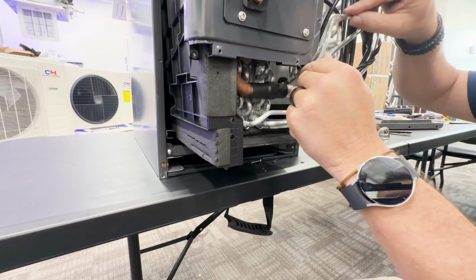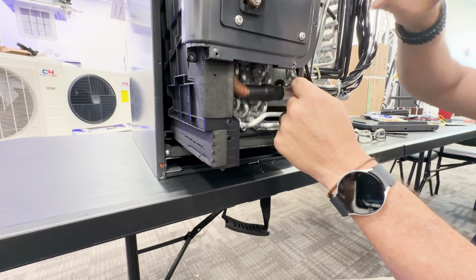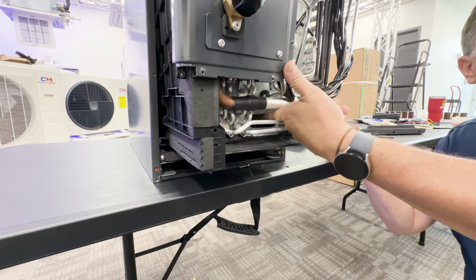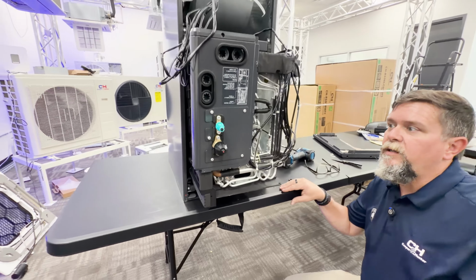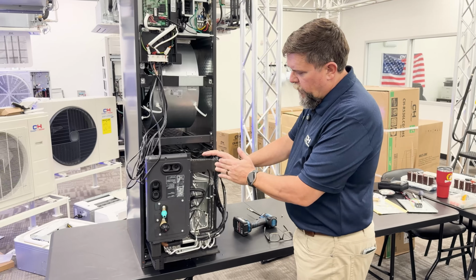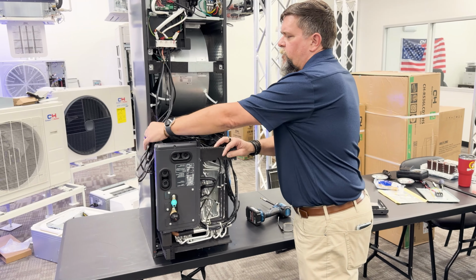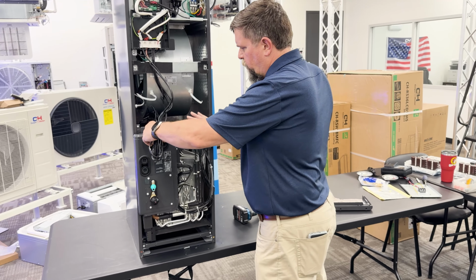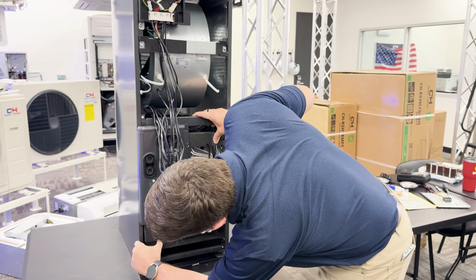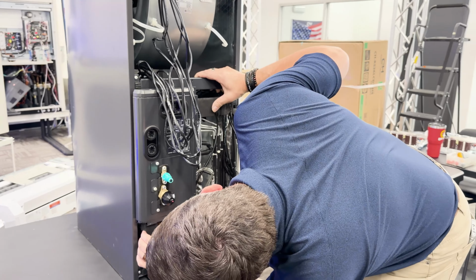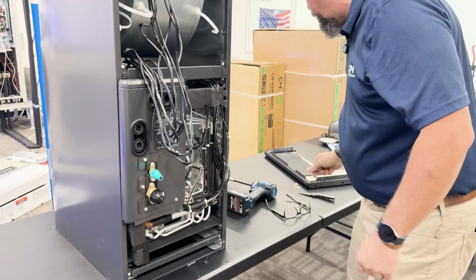Gently tuck the wires back up here, so that way it's in the airstream when it's on the downflow side, getting an accurate room air reading. With the wires protected and the thermistor relocated, now we can gently push the coil back in. Make sure everything's lined up, and down here at the bottom, let's not forget that one extra screw.